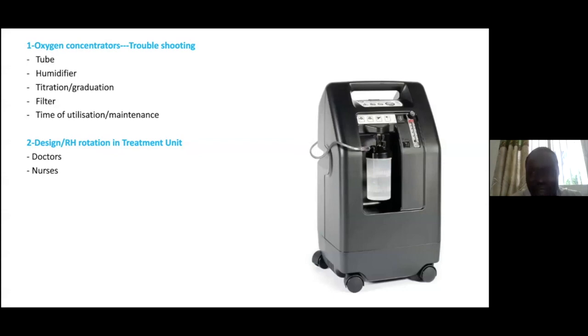So I noticed that, yes, the patient is on an oxygen concentrator, but maybe something is missing between the bottle where we put the water to humidify. So maybe there is leakage, there is an opening between the tubes that take the oxygen from the concentrator to the patient and also at the bottle. So when we humidify it, the oxygen is also going outside, and the patient will never benefit from the oxygen. This is the reason why in the last week, with most of our patients, even though we put the oxygen concentrator, we never got the maximum saturation we need, or even when we shifted to the oxygen cylinder, we were still facing the same problem.